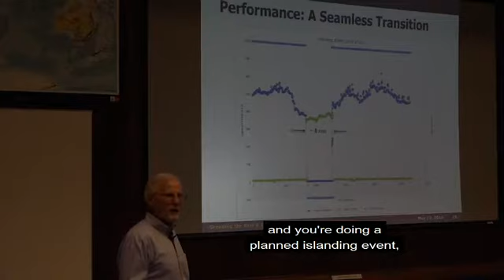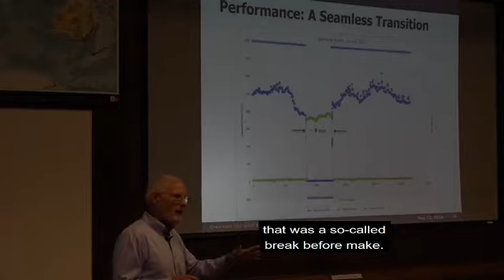I talked about a seamless transition. If the battery and the PV array have enough power to supply the whole load, and you're doing a planned islanding event, you can do it seamlessly. The other times the microgrid took over during an unplanned outage, that was a so-called break-before-make: it disconnected and then reconnected. But in a planned transition, it can connect in a fraction of a second, so there's almost no interruption in power.